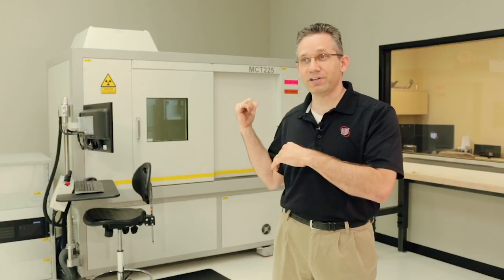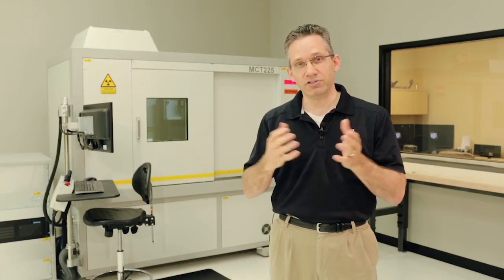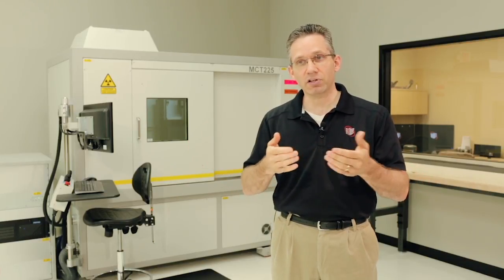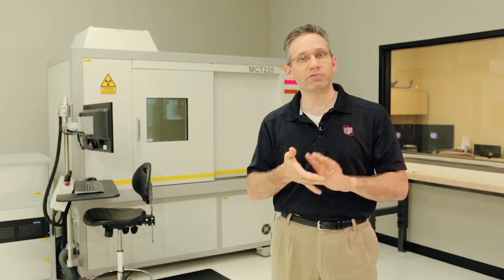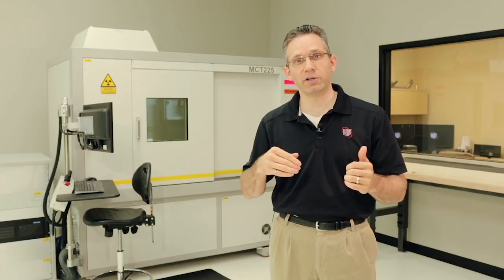This won't accept a very large part per se, you won't put a two meter part in there, but that's just the way the scale is going. That's a little higher than the accuracy that's listed for this machine, but that's normal for measurement uncertainty because we're adding other factors than what the manufacturer would normally include.